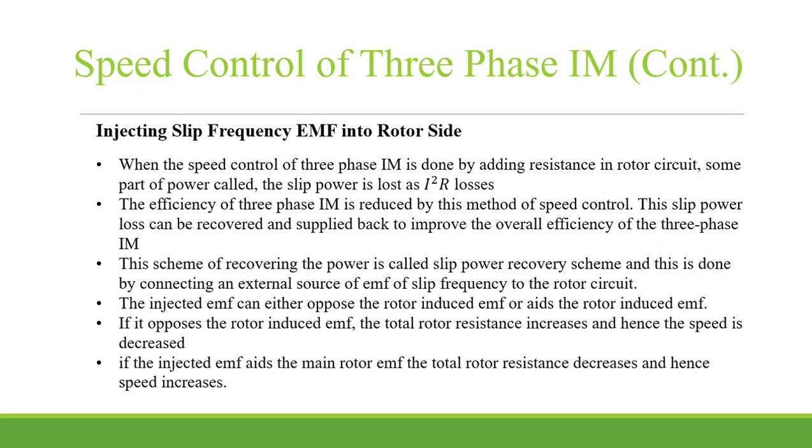If it is opposing the rotor induced EMF, then the effective rotor resistance will increase, so the speed will decrease. And if the injected EMF adds up with the main rotor EMF, then the rotor resistance will decrease and the speed will increase.